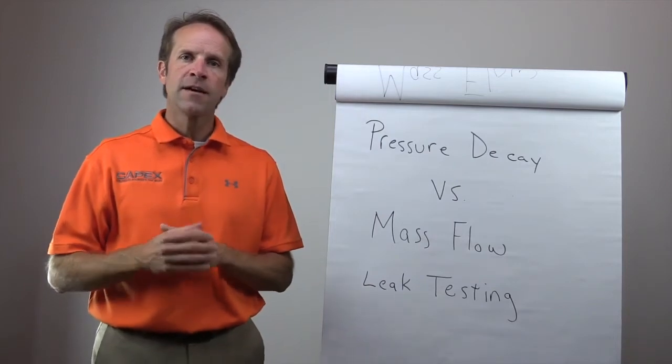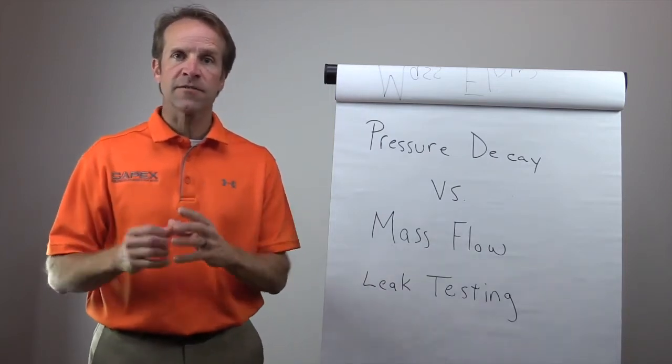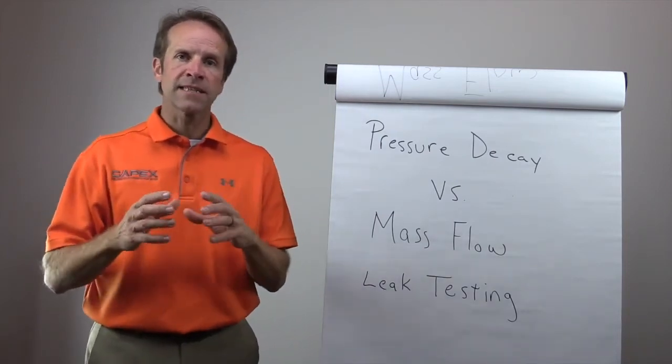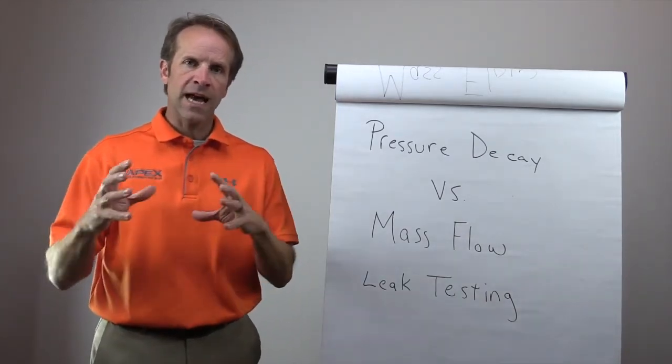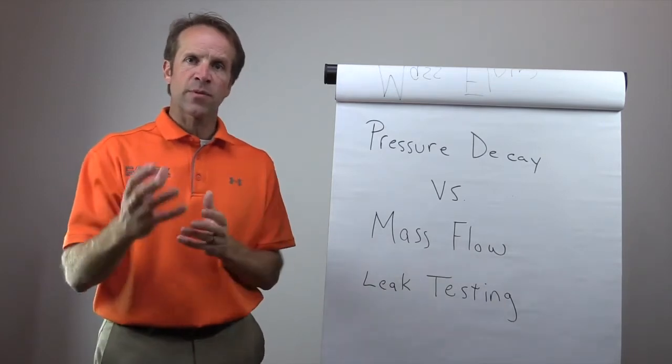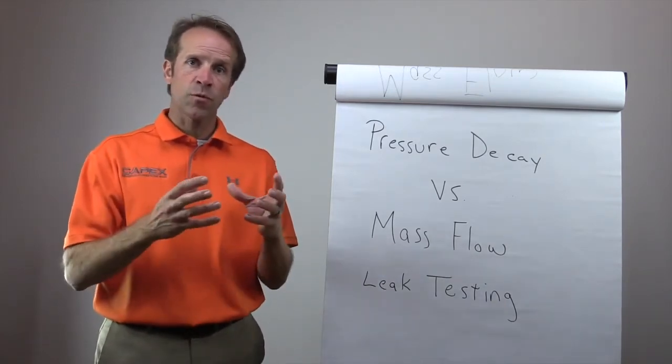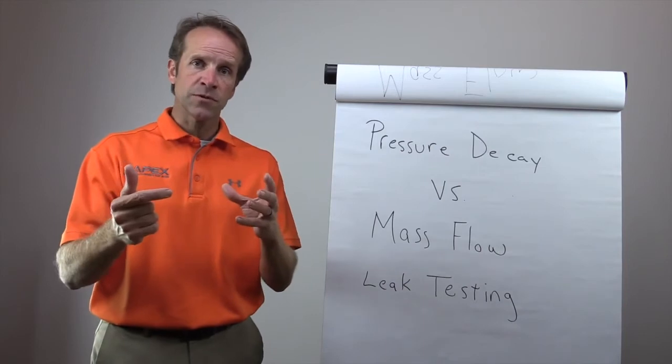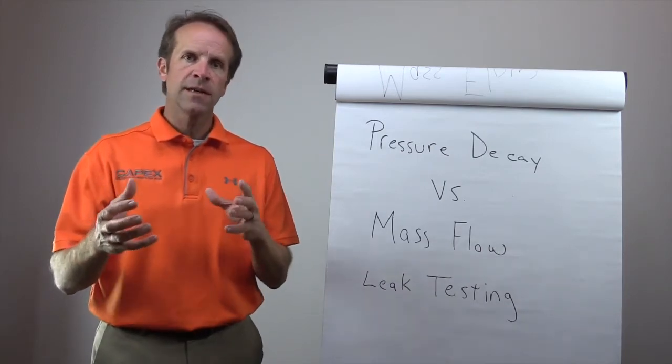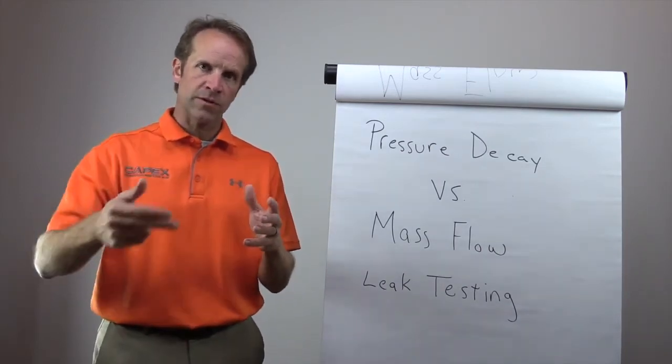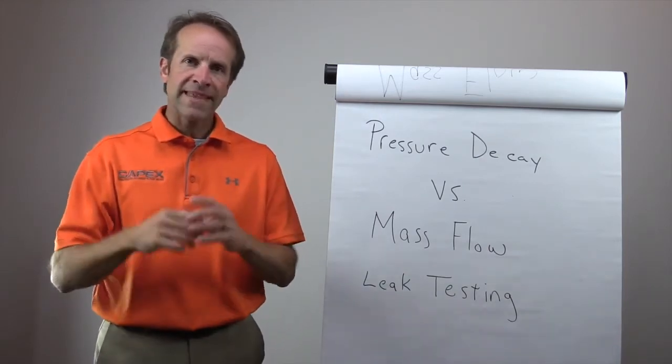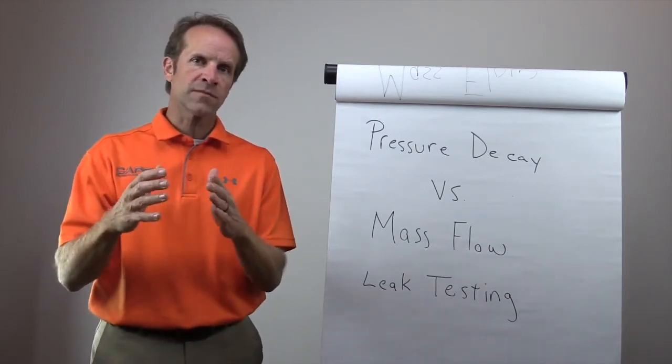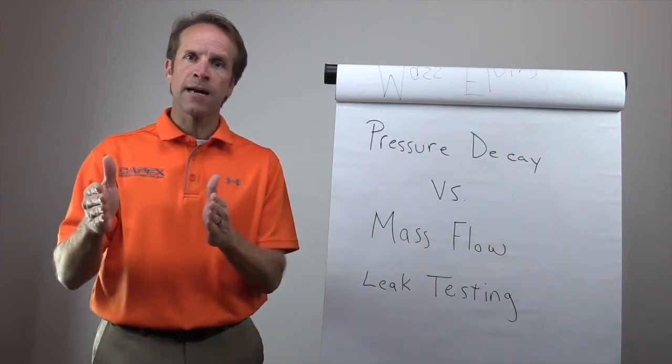So pressure decay leak testing. First, let's discuss the definition. Pressure decay leak testing is the measurement of a pressure loss over time. So we have a circuit that is pressurized. That circuit includes your part and obviously a transducer to measure the pressure change of your part, as well as the pressure lines going to the part, the manifold that's in the instrumentation. That circuit pressure loss is measured over a certain period of time.